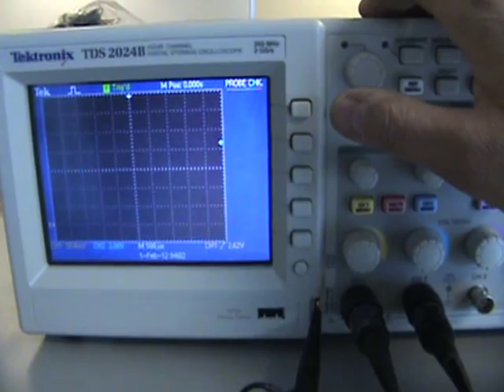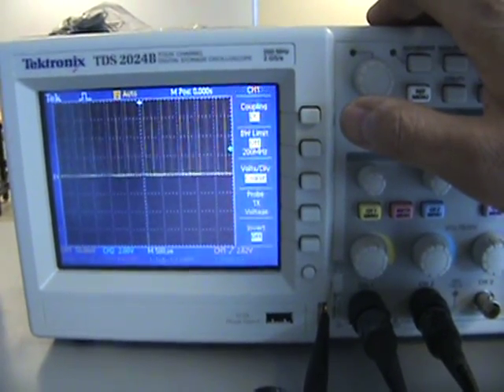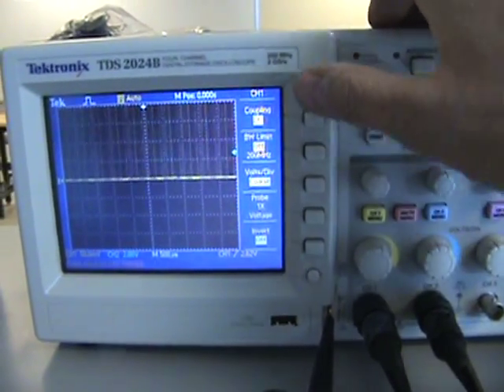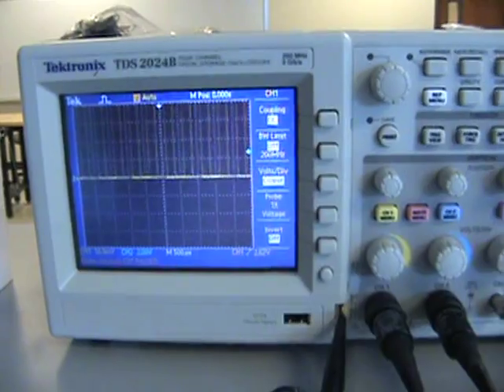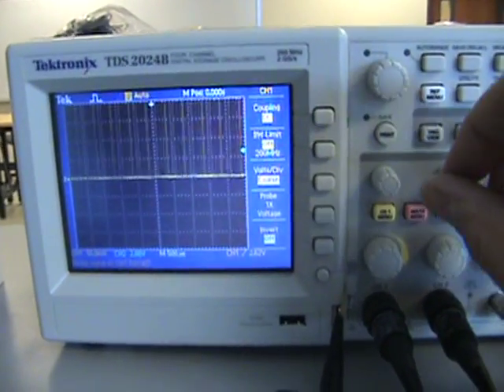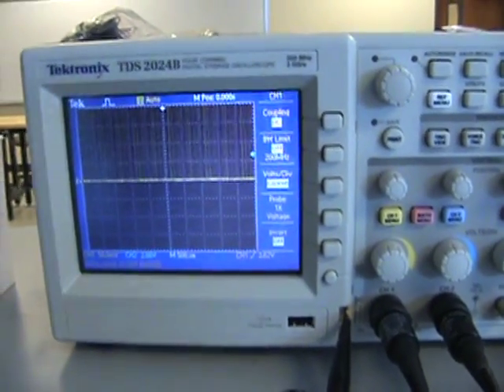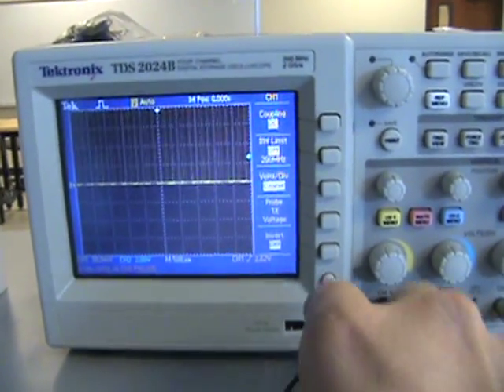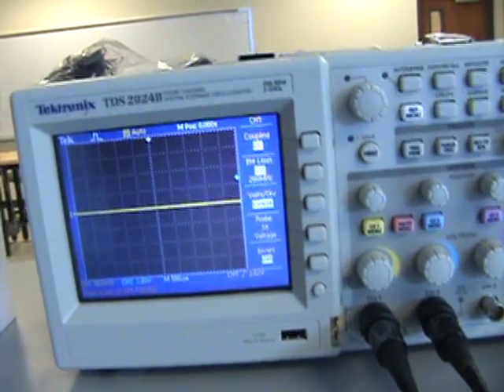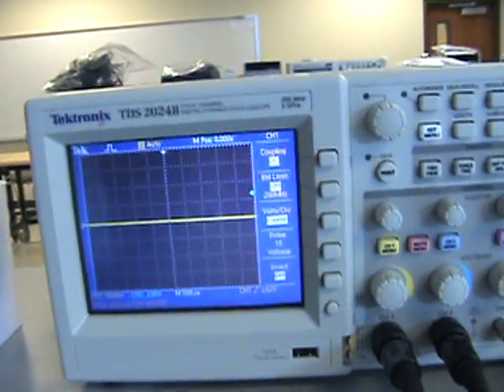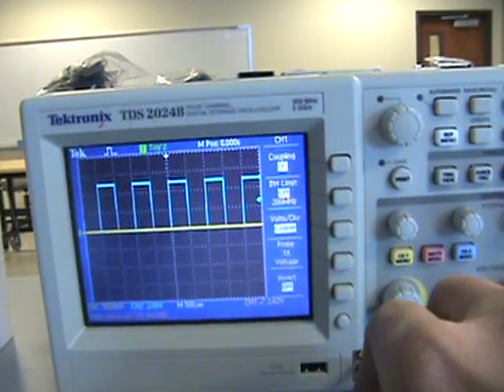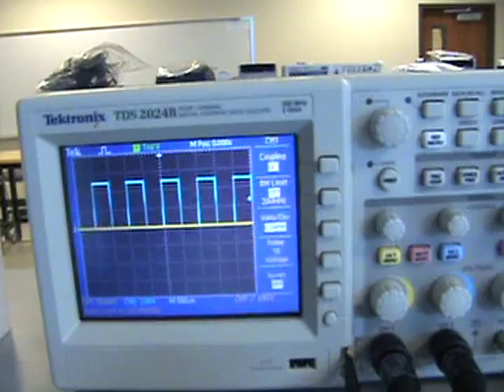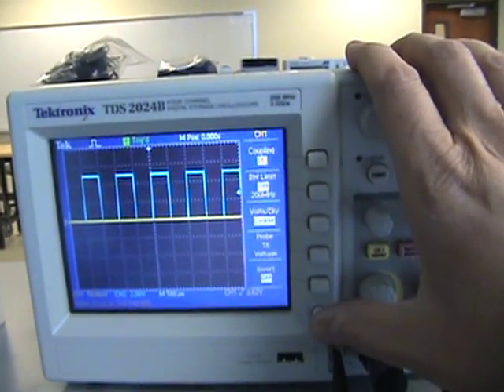That's good to go. And now we have our signal coming in. You basically repeat the process with your other probe. You can only hook up one probe at a time, and then probe check.